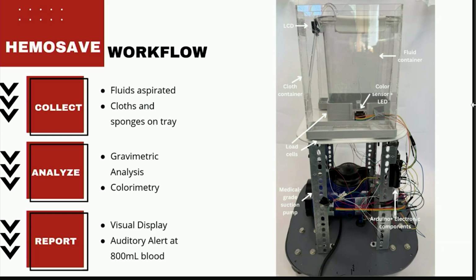Through end-user feedback, when I went back for a second summer in Uganda, we discovered that they don't just want to use suction in the ORs, also cloths and surgical sponges are a really significant portion of how waste is managed. And so we added these two trays on the side. Prior to the surgery, all the clean cloths and gauze that will be used is loaded into one of the trays. During the surgery, those are used and replaced into the second tray, and a differential measurement of the mass is taken between the two to get the total volume of blood collected in the sponges. And then that total volume is calculated and output to the user on a digital display. But we know they're not going to be looking at that all the time, so we also added an alarm which will sound once 800 mils, which is a physiologically dangerous amount of blood to be losing, is reached.